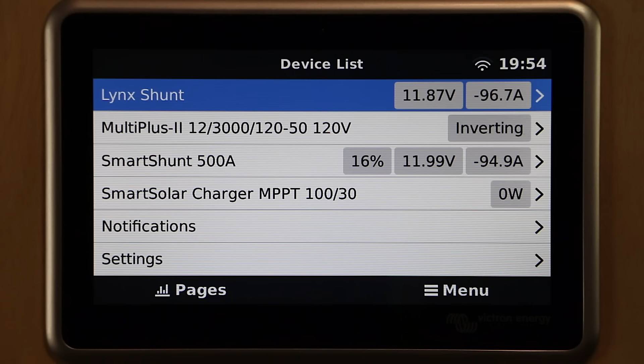If I take a reading, I'm going to zero out my clamp meter. We're at 96.8, 96.9 amps. So this is 94.9, almost 2 amps off. This is within 0.3 amps. It's still not the same as the multimeter, but it is a couple amps higher than the SmartShunt.